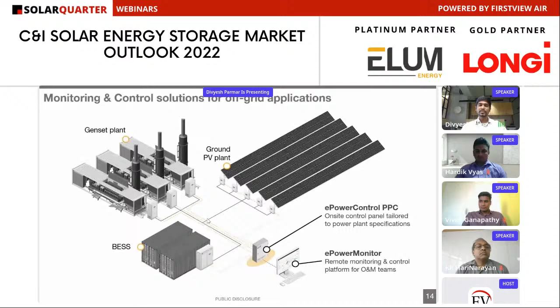Now we will move to our next application, which is the off-grid microgrid or island application. Here you can see there is a PV plant consisting of PV panels, PV inverters, a thermal plant with the backup gensets, and a battery storage with the BMS and PCS. So here basically there are two options. Either gensets are running as a primary source or the grid forming source, or batteries are running as a grid forming source.